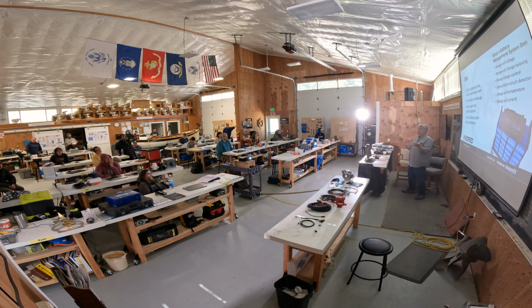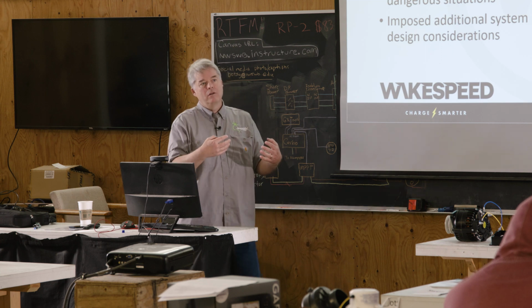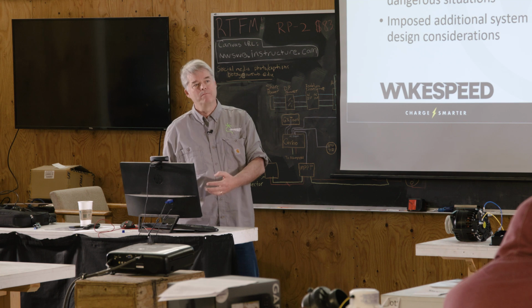Now, again, with Lithionics, they offer their integrated BMSs now. And the only thing on the top of it is a CAN port that we use. Inside, I don't know the exact structure, but I think they've got one BMS with wires that go out and sense the voltages and stuff. They don't have it distributed. It's all on one circuit board. That type of architecture is how each battery manufacturer chooses to approach the problem.